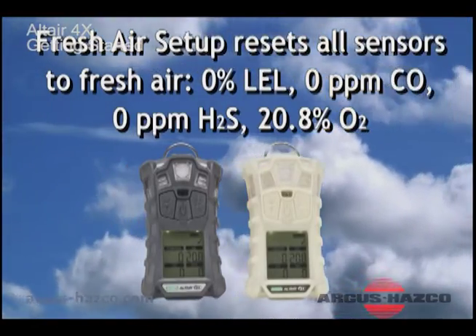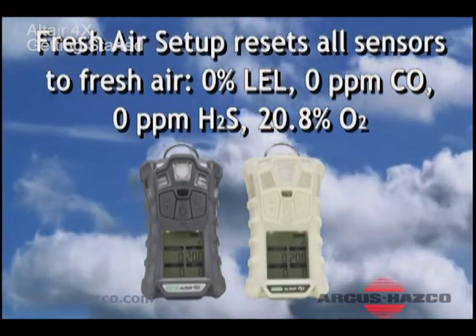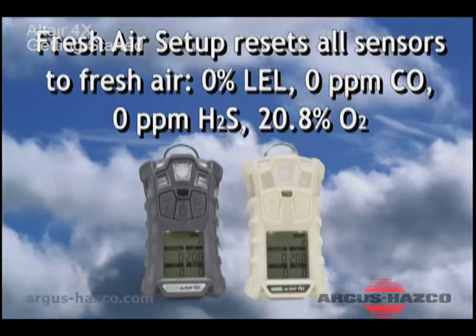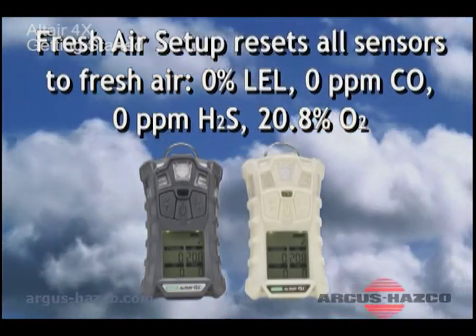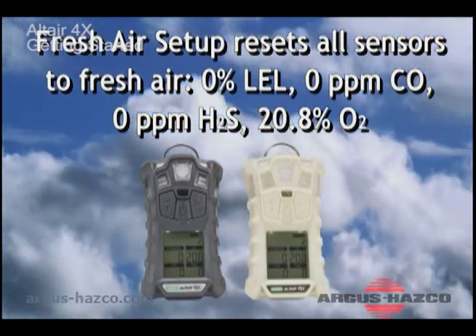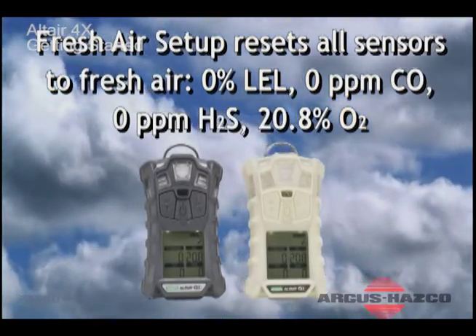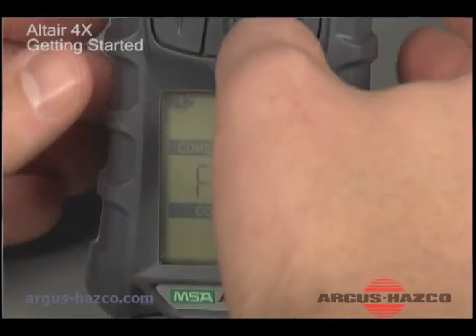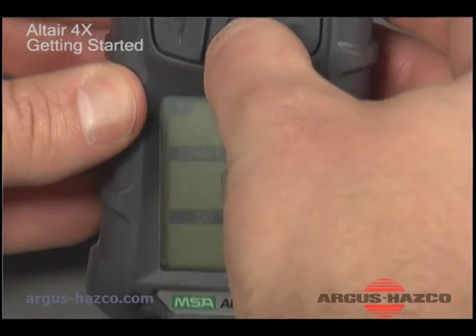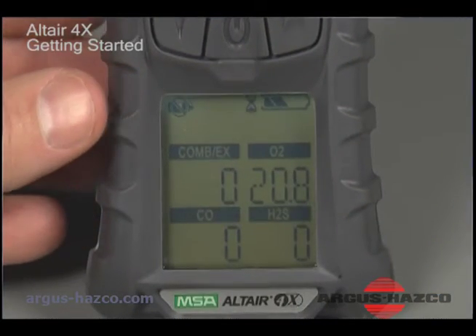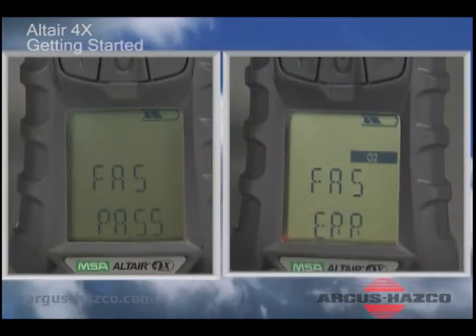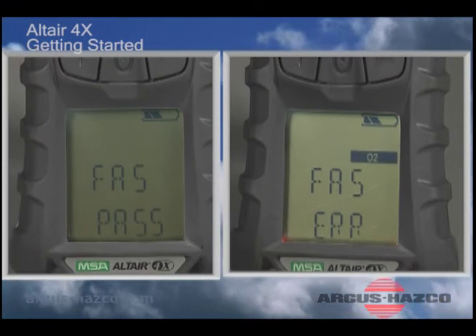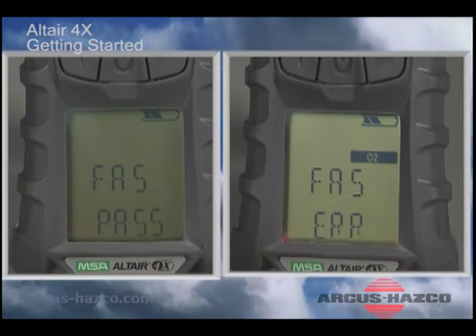Fresh Air Setup allows users to reset all sensors to fresh air values: 0% LEL, 0 ppm carbon monoxide, 0 ppm hydrogen sulfide, and 20.8% oxygen. To run Fresh Air Setup at this time, simply push the Center or Accept button. FAS Pass or FAS Error will quickly display. If FAS Error displays, a full instrument calibration should be performed.